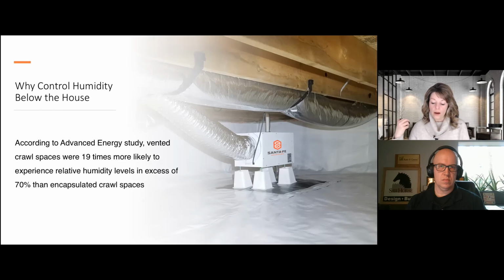So a couple years ago here in Northern Virginia, we had 2 Habitat homes right next to each other, same designs, everything. And we went in and encapsulated the crawl spaces. And we know that in building code, there are several different options for conditioning a crawl space once you close it up. The one that we see most often is using supply air from the HVAC system to condition the crawl space. So in one of the homes, we used supply air to condition the crawl space, and in the other one, we put in a dedicated dehumidifier.